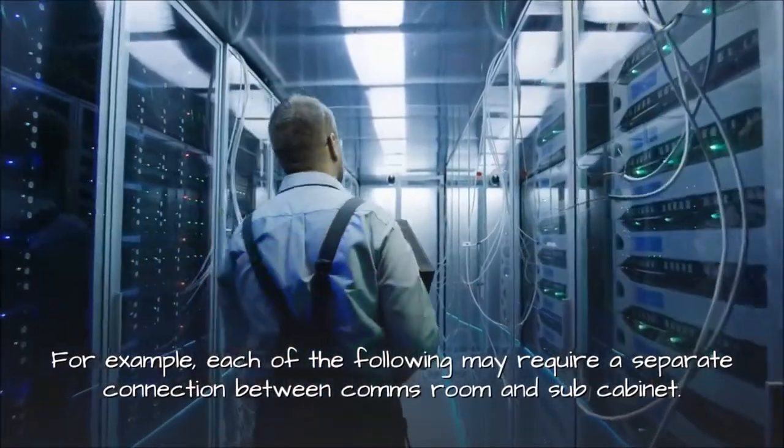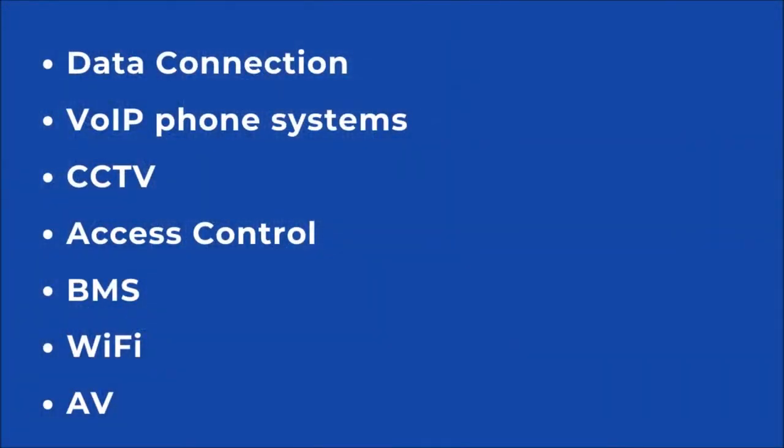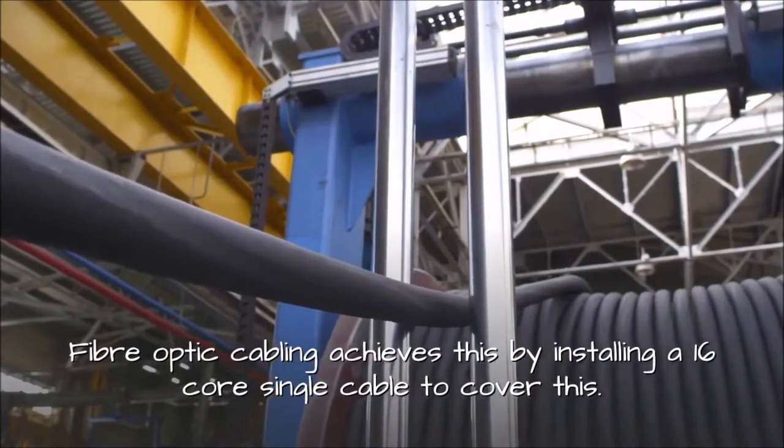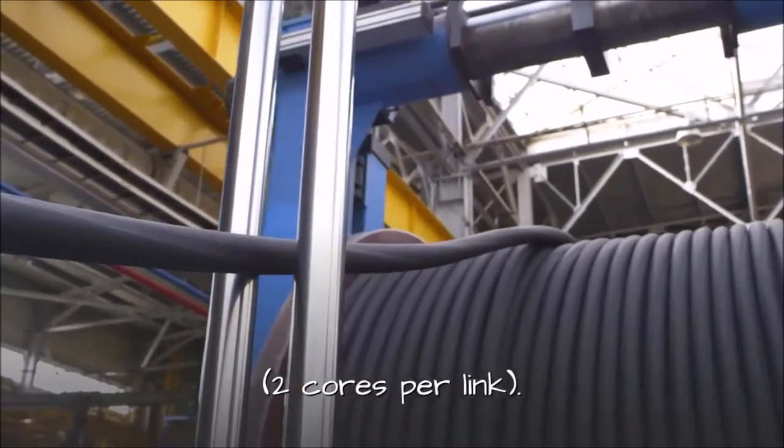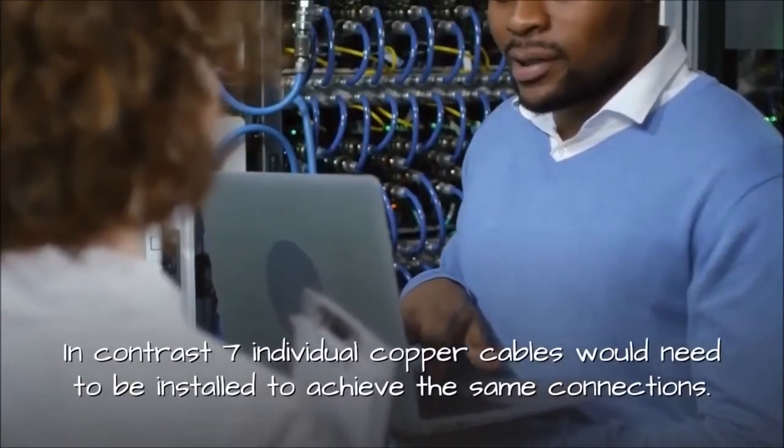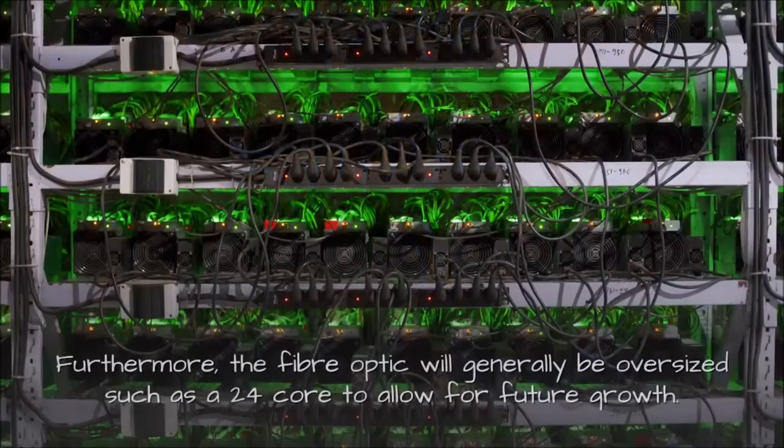For example, each of the following may require a separate connection between comms room and sub cabinet: data connection, VoIP phone systems, CCTV, access control, BMS, Wi-Fi, audio visual. Fiber optic cabling achieves this by installing a 16 core single cable to cover this. Two cores per link. In contrast seven individual copper cables would need to be installed to achieve the same connections. Furthermore, the fiber optic will generally be oversized such as a 24 core to allow for future growth.